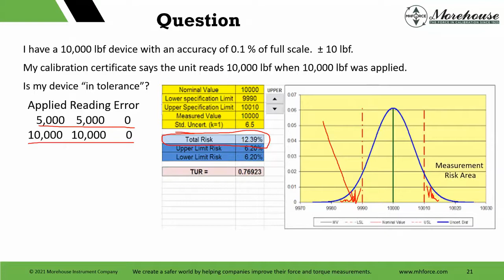Same thing with measurements. So that's that measurement risk error. And if measurement uncertainty is not being reported properly by your service provider, there's no way to know if the device is in tolerance, and you do not have a traceable measurement.